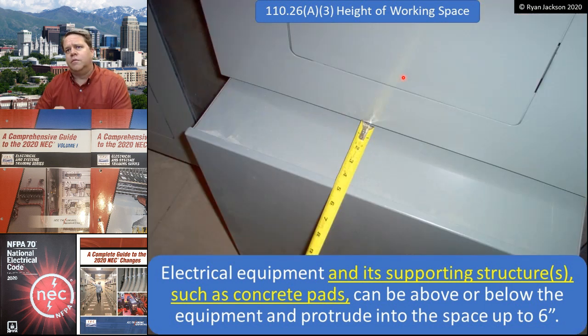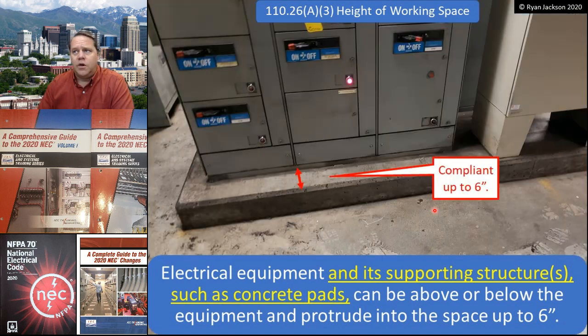That's a very reasonable allowance, because when I'm working inside of a panel, I'm not going to be standing with my nose right in there and my toes touching it. I'm going to be at least 6 inches away. So this seems like a nice allowance. The change here is that it's now including the supporting structure for the electrical equipment, like a concrete pad, or what we commonly call a housekeeping pad.